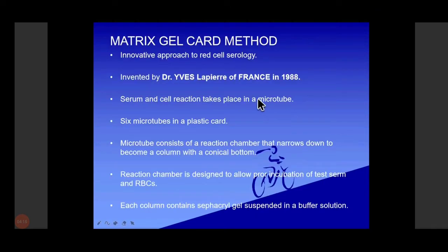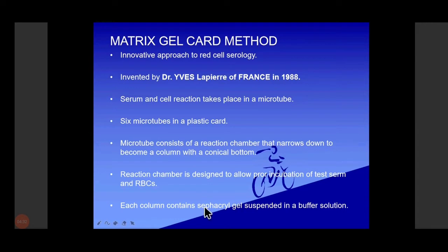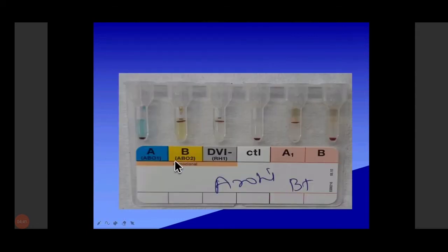Now we can see the matrix gel card method. It is an innovative approach to red cell serology, invented by Dr. Lapierre of France. Serum and cell reactions take place in a microtube. There are six microtubes in the plastic card. This microtube consists of a reaction chamber that narrows down to become a column with a conical bottom. Each column contains a sephacryl gel as the separation medium.